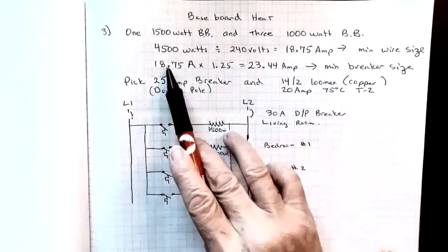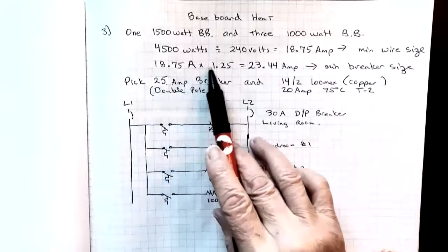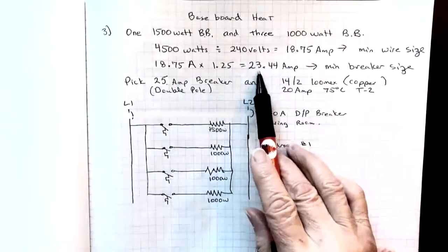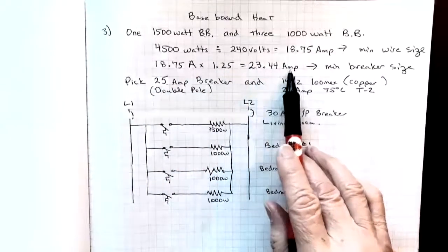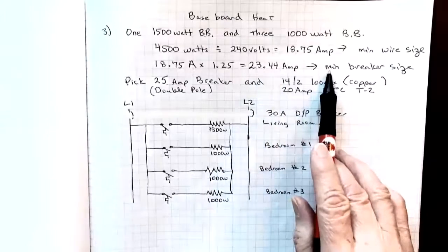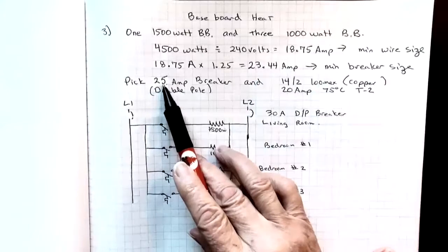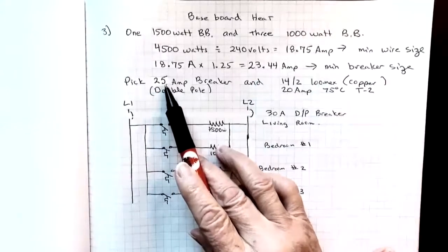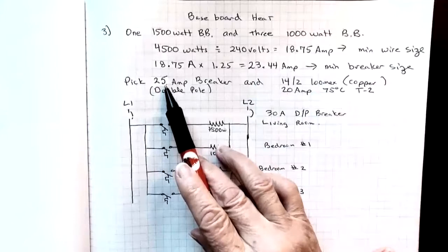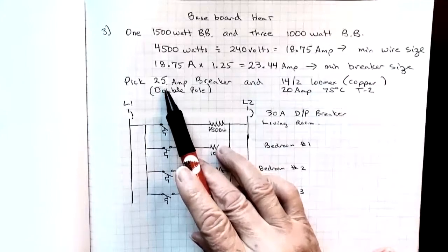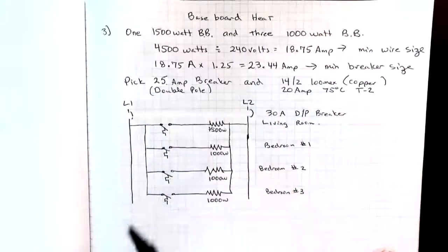To find the minimum breaker size, it's 18.75 times 1.25 giving me 23.44 amps, the minimum breaker size. I go to table 13, I pick a 25 amp breaker. If the brand that you are installing in panel does not have a 25 amp breaker, you are allowed to go to a 30 amp breaker. Now it would be a double pole.